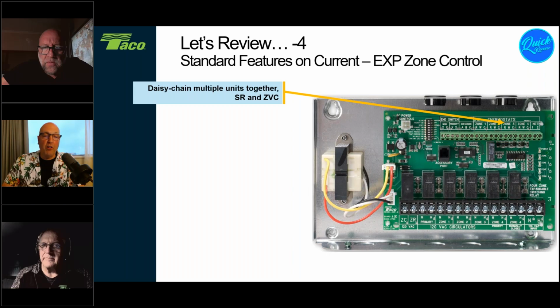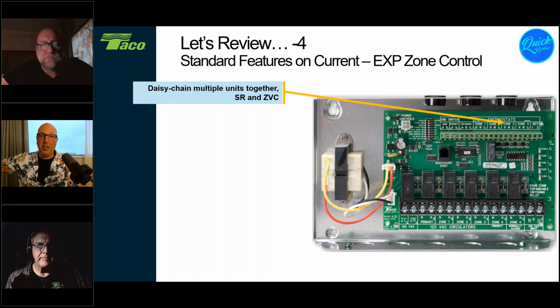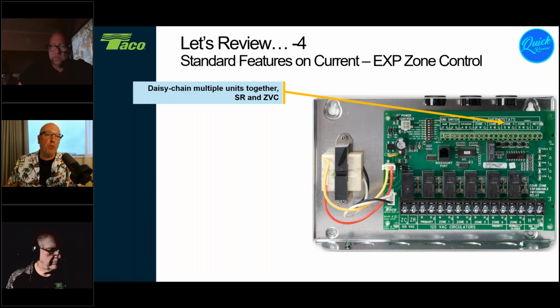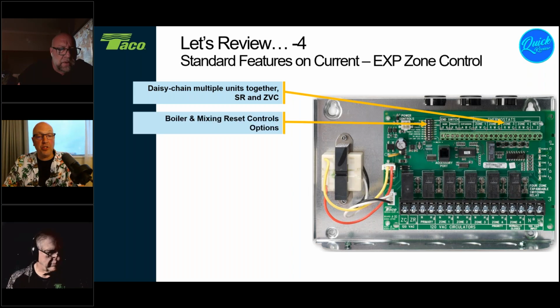All right. So the first thing that we had made on the Dash 4s was this ability to daisy chain components. We have this expansion terminal, which means we could go from a ZVC to another ZVC to an SR panel to another ZVC. Didn't matter what you had. But you were able to daisy chain these all together with a simple 3-wire thermostat wire, and they were able to communicate to each other. So it made wiring back to the boiler a heck of a lot easier.